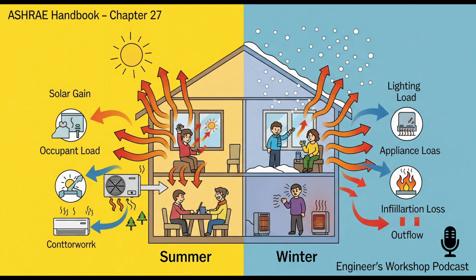Okay, so this leads to something that sounds a bit counterintuitive: heat gain versus cooling load. This is a really key concept from the sources. Instantaneous heat gain, the heat pouring into the building right this second, isn't always the same as the cooling load, which is what your AC actually needs to deal with. Wait, how could that be? If the heat's coming in, doesn't the AC just fight it?